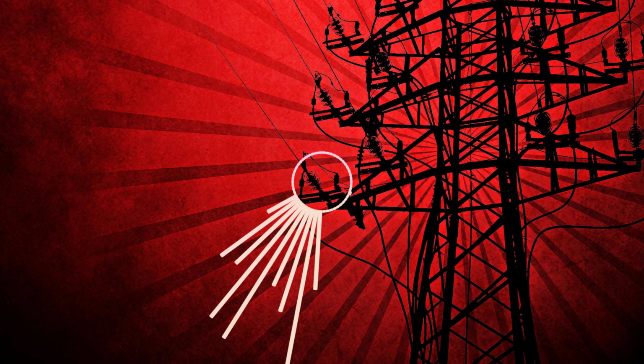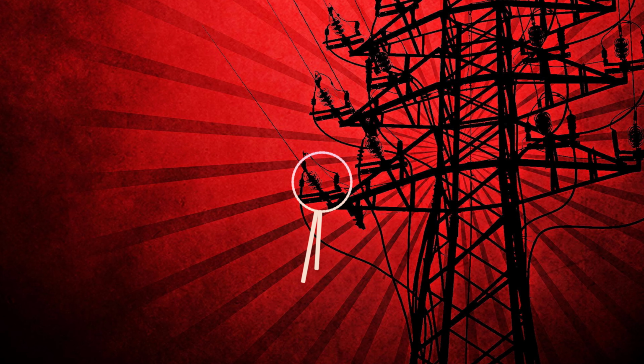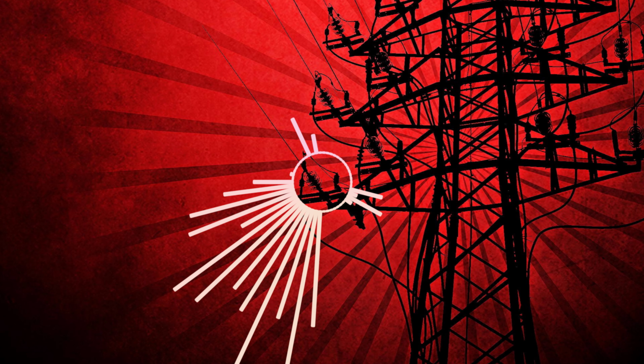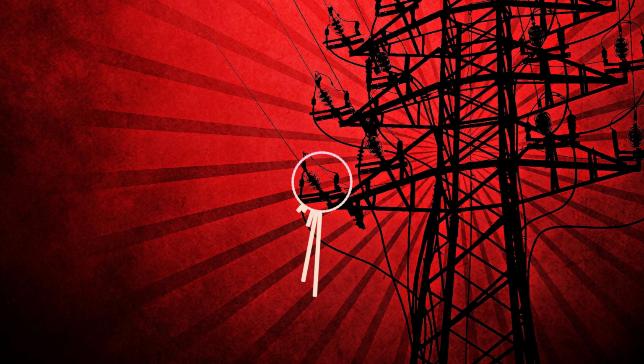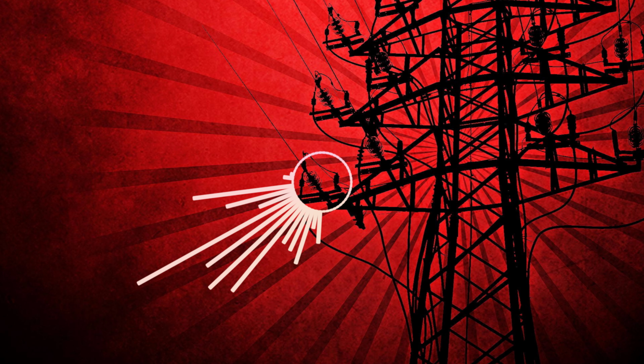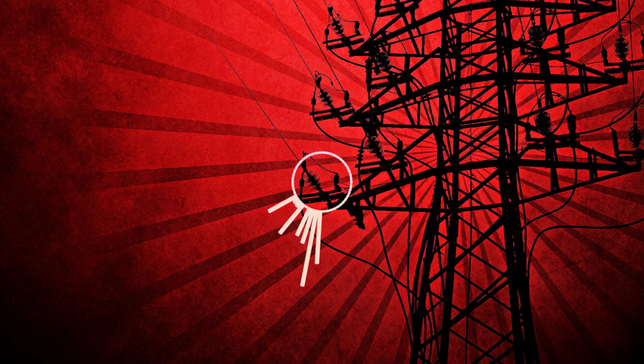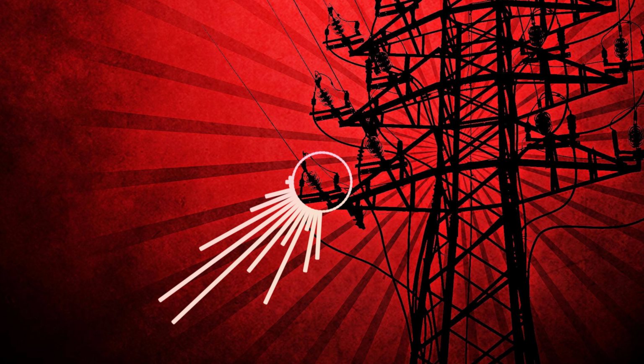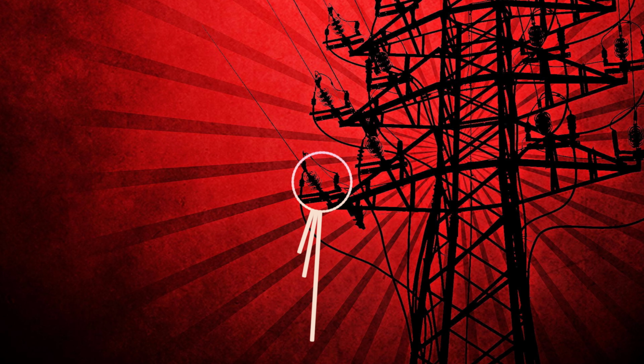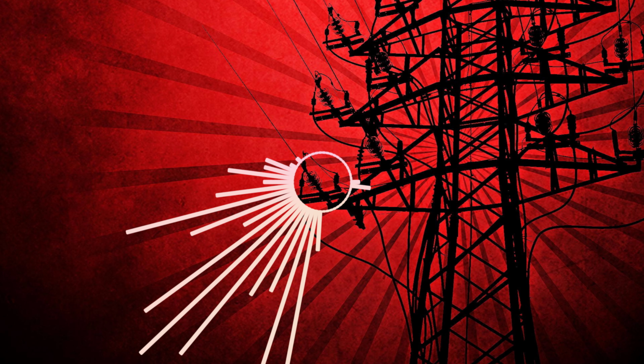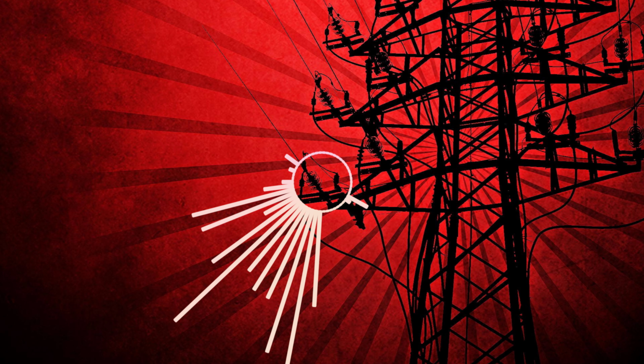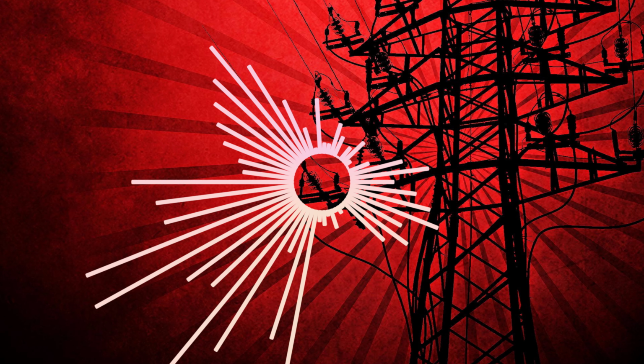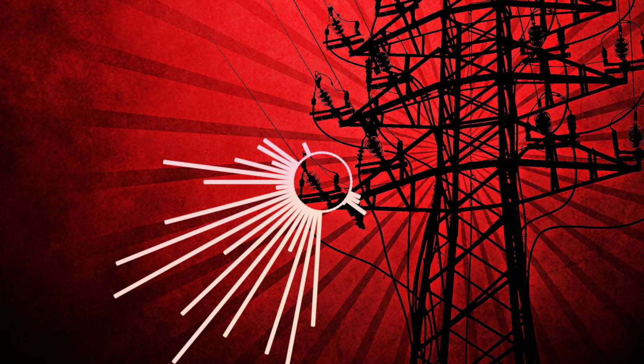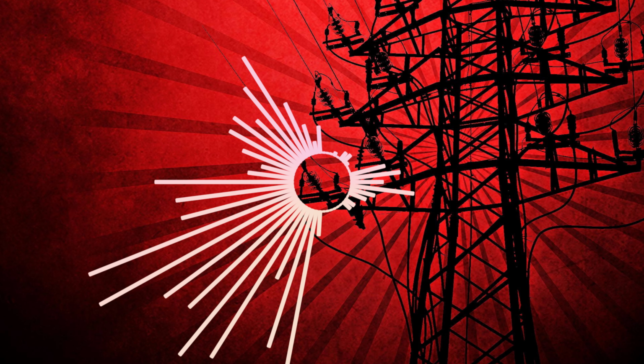If nobody updates the label, electricians might look at it and think, hey, this panel can handle 25,000 amps, but the real available fault current now might be 40,000 amps. That's a huge safety risk. The wrong equipment could fail during a fault, possibly causing equipment damage, electrical fires, or even life-threatening flash incidents.